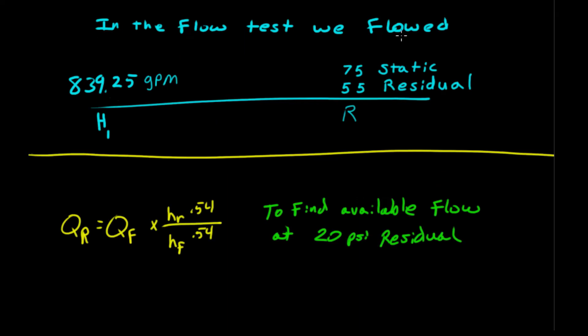In the flow test, the first one we did, we flowed 839 gallons a minute with a static of 75 or a residual of 55. We calculated that out already. As I said earlier, the problem in NFPA 291 is this one here. So that's to find our available flow at 20 PSI residual pressure.